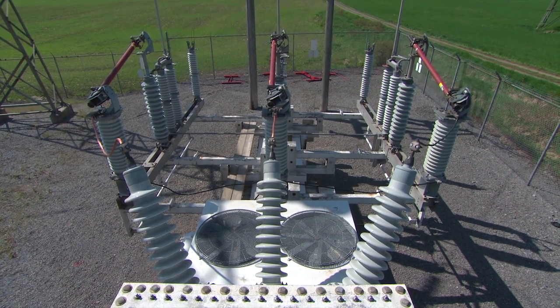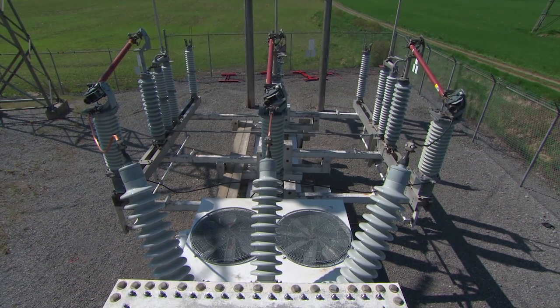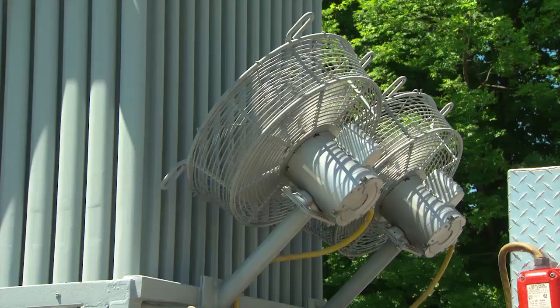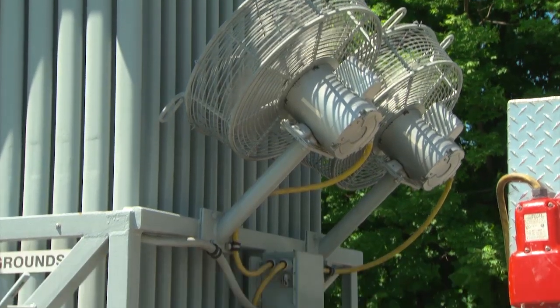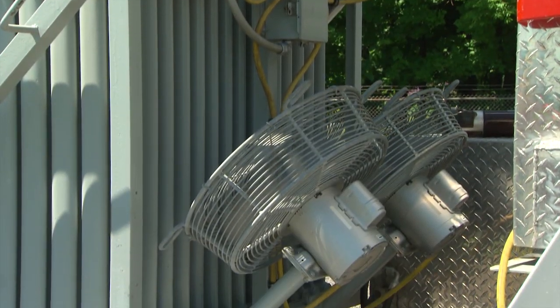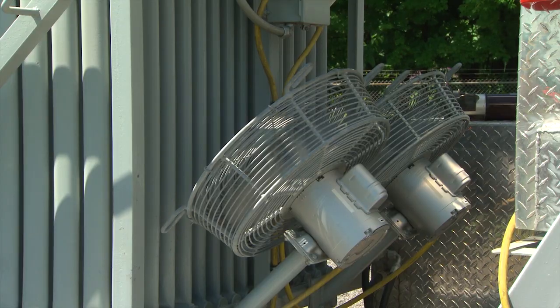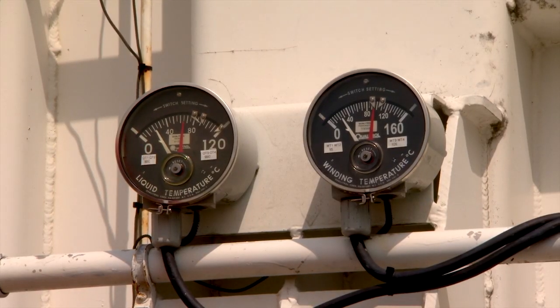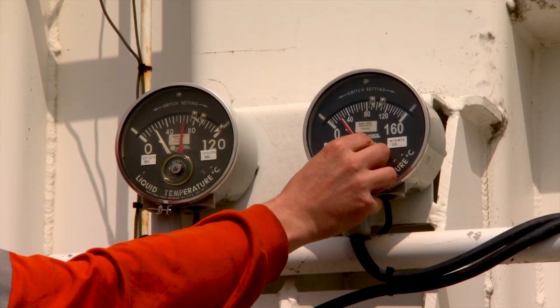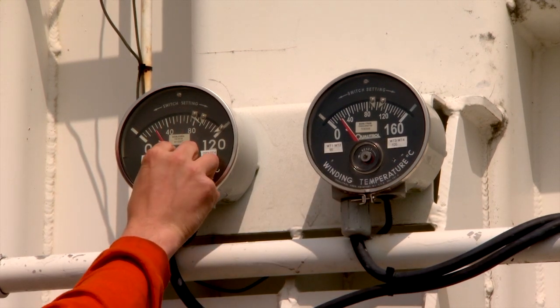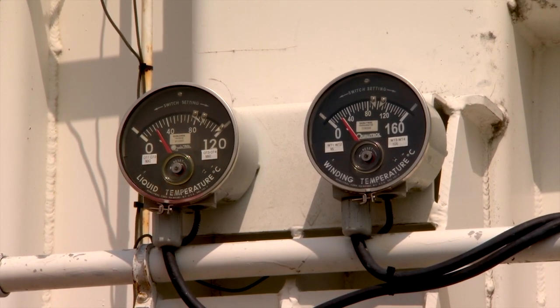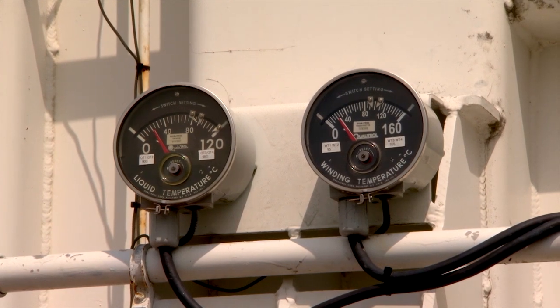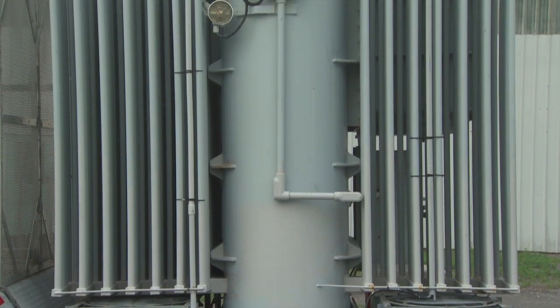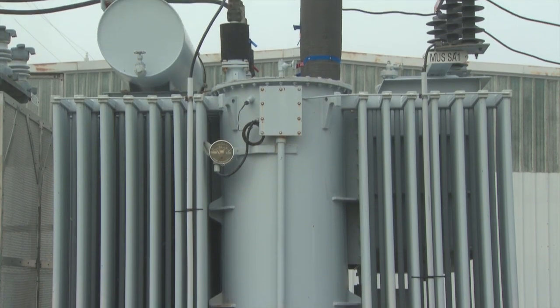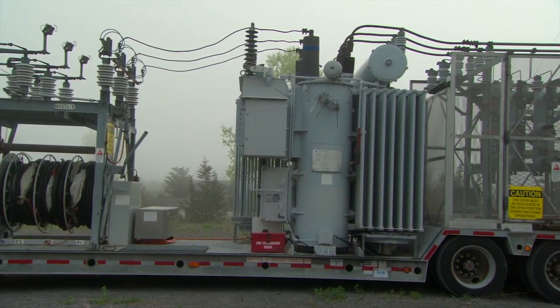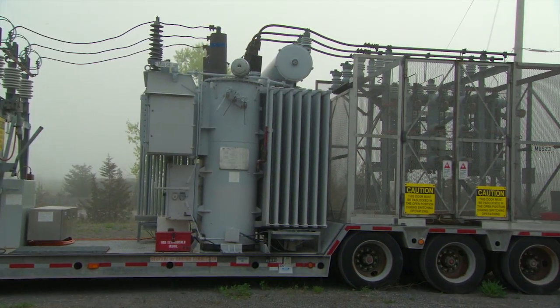Cooling equipment. The MUS cooling system consists of fans, pumps, or a combination of the two. MUS transformers with a self-cooled rating are thermostatically controlled from a temperature gauge on the bank. The cooling for these units will operate automatically as temperature increases. Some MUS transformers do not have a self-cooled rating, which means the units must have the cooling equipment operating at all times while in service.